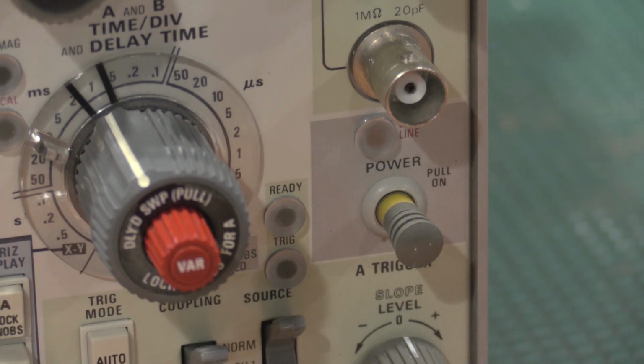It's wanting 104 volts, but I'm at 111. That's also because I've reset the regulator for the line voltage of 120 as opposed to 115 volts. So 111 is not bad. So we'll bring this back up to 120 and it comes off.